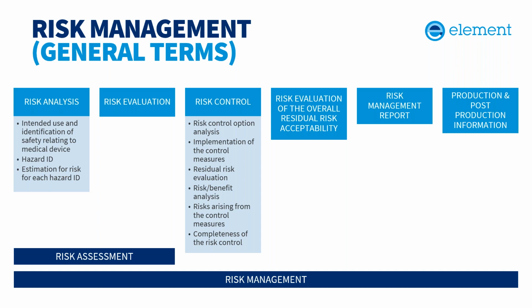And risk analysis is crucial for the evaluation of components within the broader risk management and assessment process. So in risk analysis, you're determining the significance of the risk factors you identified in the risk management process. It also qualifies the risks, things like measuring the likelihood of a hazard occurring and tolerances for certain events. In 60601, Annex F covers risk management and is focused on basic safety and essential performance.